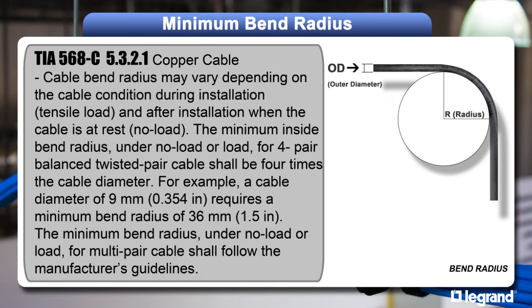Bend radius refers to the minimum radius that a cable can be allowed to bend without damaging the cable. All changes of direction on a cable run should be gradual and smooth whenever possible. For UTP cable, TIA requires a minimum inside bend radius of four times the diameter of the cable.